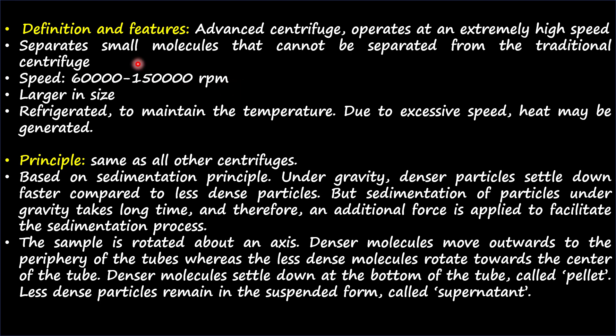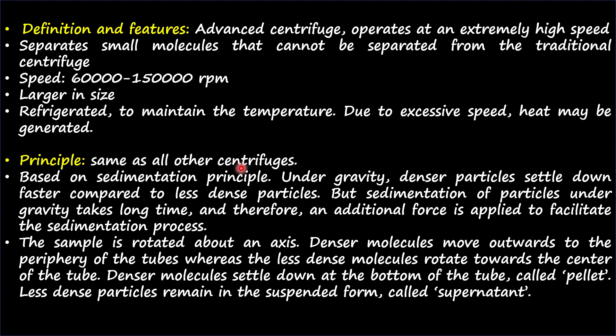It separates small molecules that you cannot separate with a traditional centrifuge. This ultra centrifuge is larger in size and it can be refrigerated, meaning you can maintain the temperature, because due to the excess speed, heat may be generated in this type of centrifuge. Hence refrigeration is required.